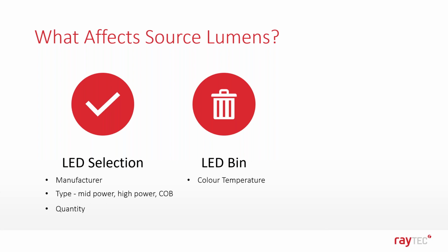One of these categories is color temperature. A lot of LEDs use a deep blue light source and then convert that light to white using a phosphor layer. So if you're looking at an LED chip, the phosphor layer is the distinctive yellow square that you see in the center of a lot of LEDs. The warmer the color temperature you select, the more work the phosphor has to do, and generally the lower the lumen output. Similarly, for color rendering index, to get a high CRI, you must use a denser phosphor layer, and generally this reduces the lumen output.